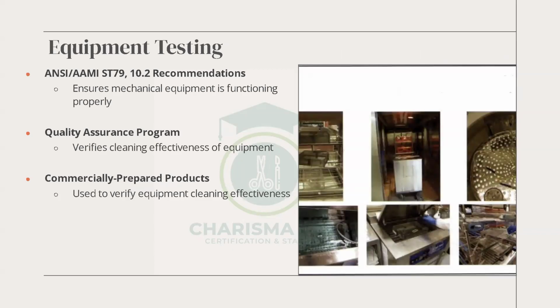Equipment testing, as I told you, we have standards and they do a lot of testing every day. Every machine has to be tested in the morning, especially when there's a fault, repairs, or a gas shut off. The testing is even done rigorously. At times, the test that you do once, sometimes you have to do 3 times before you can start the normal reprocessing. Okay, so that is equipment testing. There are standards from ANSI and AAMI. They have recommendations which ensure mechanical equipment is functioning properly. These are standards that you have to follow.